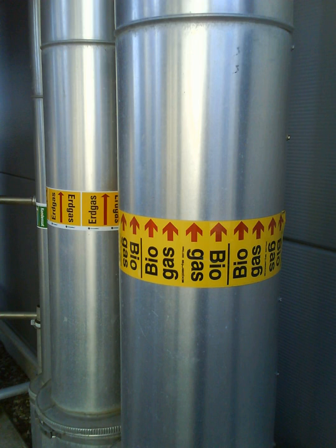The most prevalent method is water washing, whereby high-pressure gas flows into a column in which the carbon dioxide and other trace elements are scrubbed by cascading water running counter-flow to the gas. This arrangement can deliver 98% methane, with manufacturers guaranteeing maximum 2% methane loss in the system. It takes roughly between 3% and 6% of the total energy output in gas to run a biogas upgrading system.